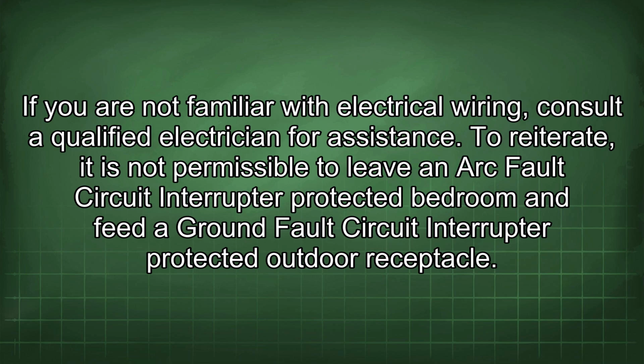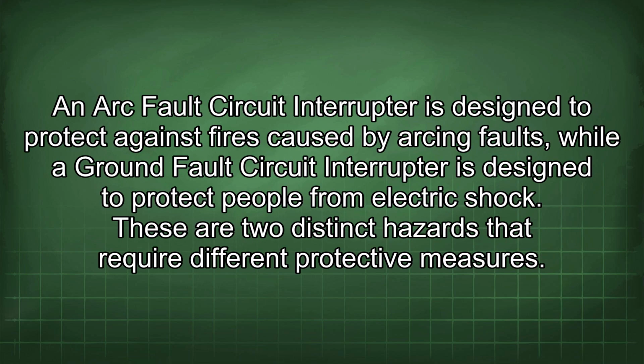To reiterate, it is not permissible to leave an arc fault circuit interrupter protected bedroom and feed a ground fault circuit interrupter protected outdoor receptacle. An arc fault circuit interrupter is designed to protect against fires caused by arcing faults, while a ground fault circuit interrupter is designed to protect people from electric shock. These are two distinct hazards that require different protective measures.